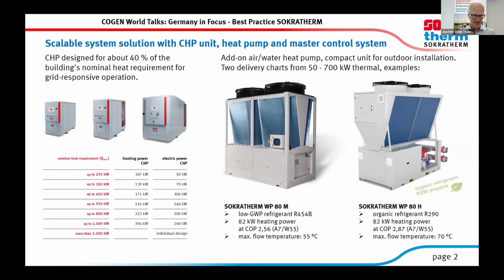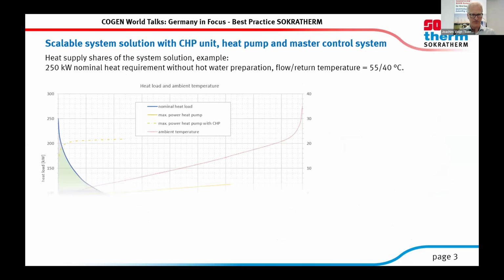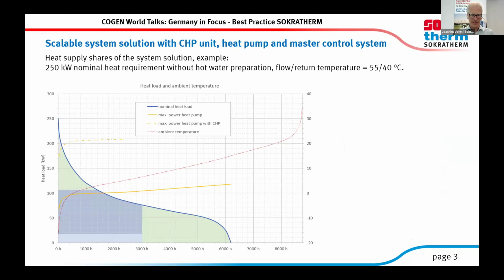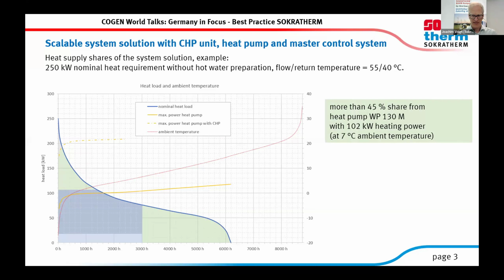And with this system solution, the heat demand of a building can be provided like you see it in this sample curve. It's just an example for 250 kilowatt heat requirement. So the smallest possible solution from our side. And if you take a look at the shares of heat which can be provided to a building or heating network, it's about 45% coming from the heat pump, with about 100 kilowatt heating power at 7 degrees ambient temperature.